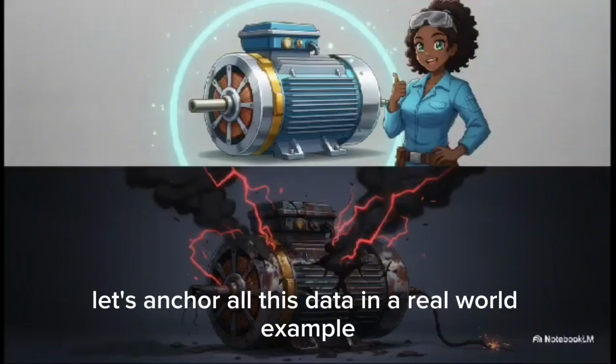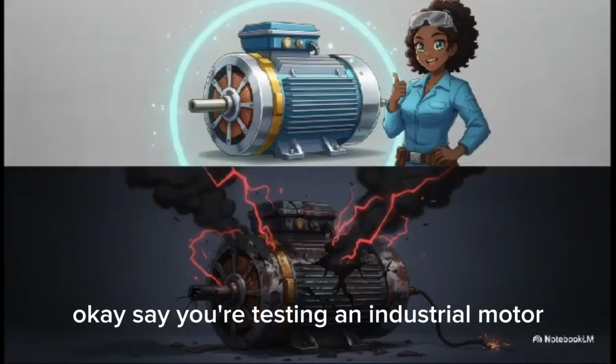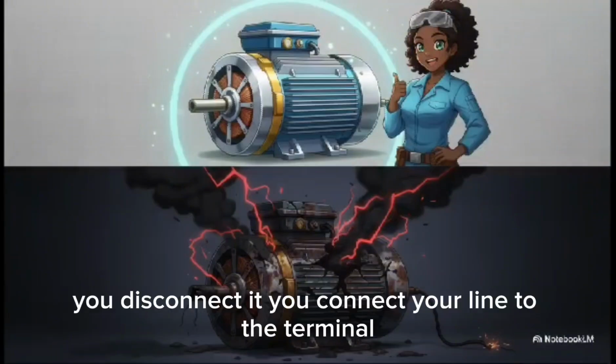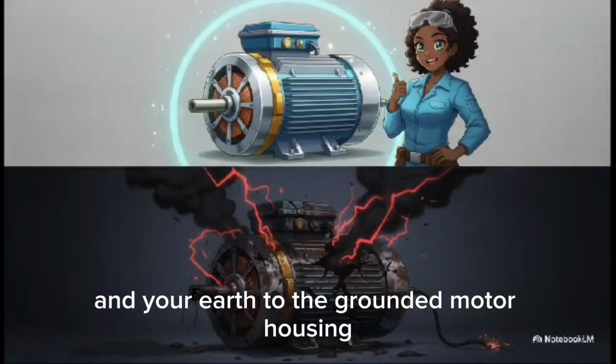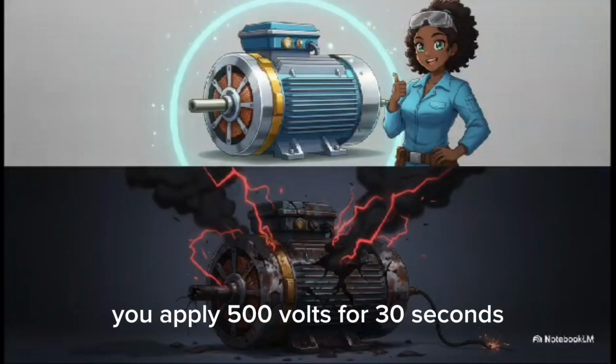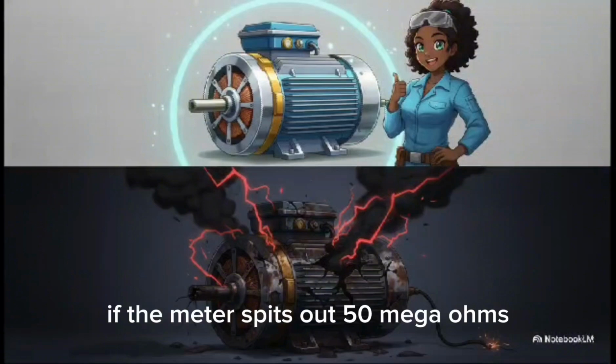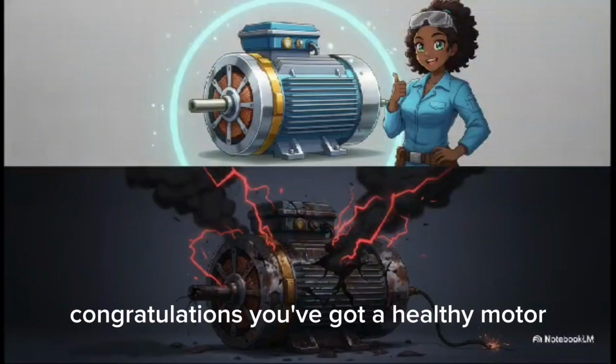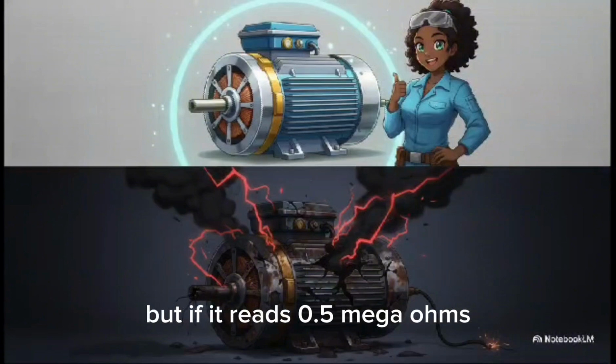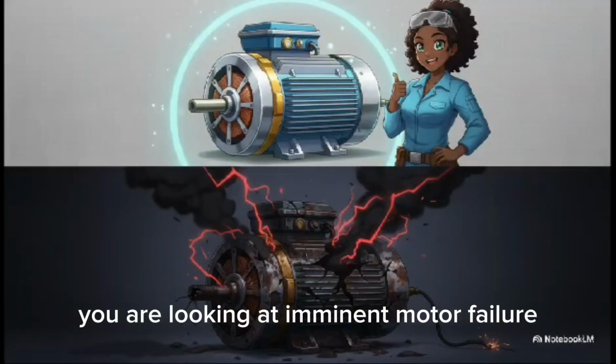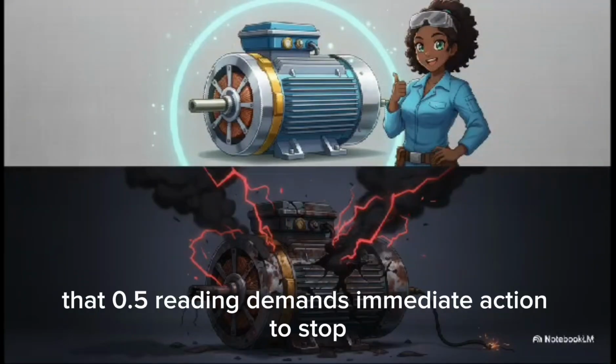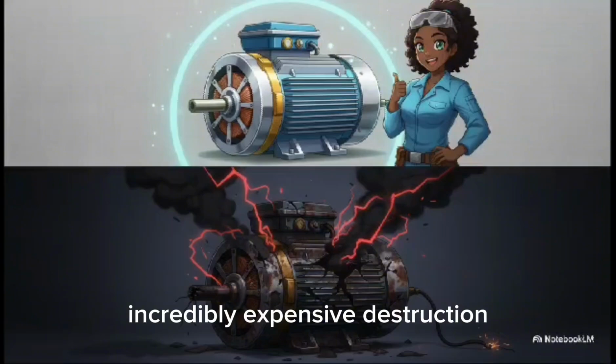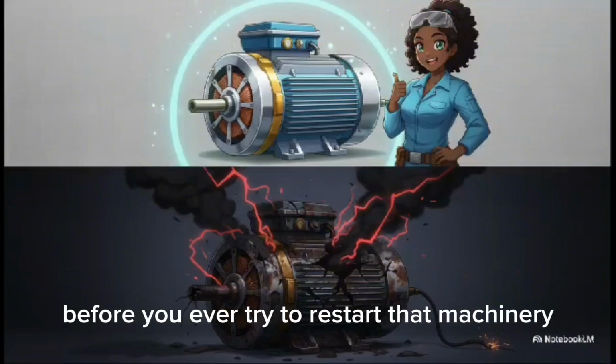Let's anchor all this data in a real-world example, okay? Say you're testing an industrial motor. You disconnect it, you connect your line to the terminal, and your earth to the grounded motor housing. You apply 500 volts for 30 seconds. If the meter spits out 50 megaohms, congratulations, you've got a healthy motor. But if it reads 0.5 megaohms, you are looking at imminent motor failure. That 0.5 reading demands immediate action to stop incredibly expensive destruction before you ever try to restart that machinery.